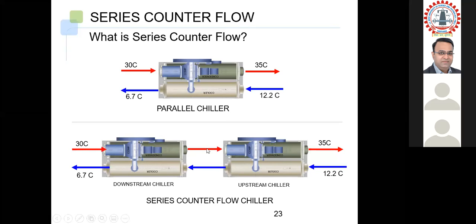But in a series counterflow arrangement, we put two chillers in series in a way that the first chiller receives 12.2 degrees centigrade chilled water. It cools it down, and that cooled water enters the second chiller, the evaporator portion, and then goes out at 6.7 degrees centigrade. On the opposite side, the condenser side, it receives water at 30 degrees centigrade from the cooling tower. It heats up the water, and the same heated water enters the second chiller and exits at 35 degrees centigrade. So this is called series counterflow, when we put two chillers in series arrangement.